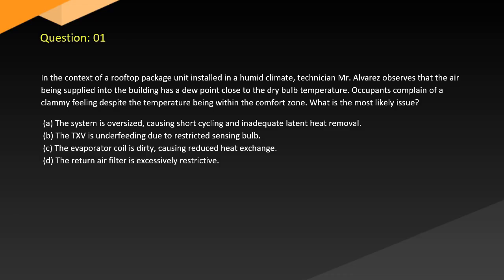A. The system is oversized, causing short cycling and inadequate latent heat removal. B. The TXV is underfeeding due to restricted sensing bulb. C. The evaporator coil is dirty, causing reduced heat exchange. D. The return air filter is excessively restrictive.